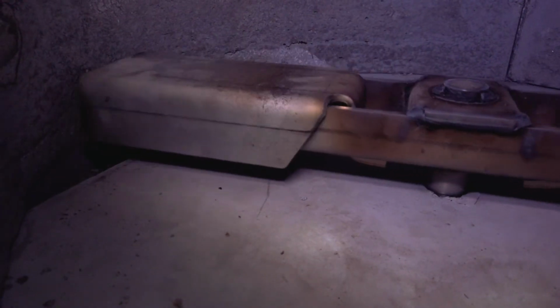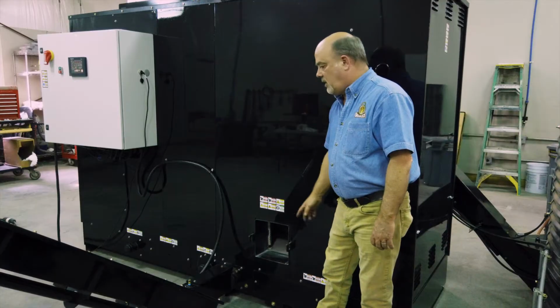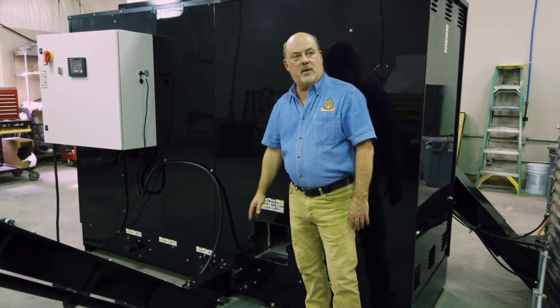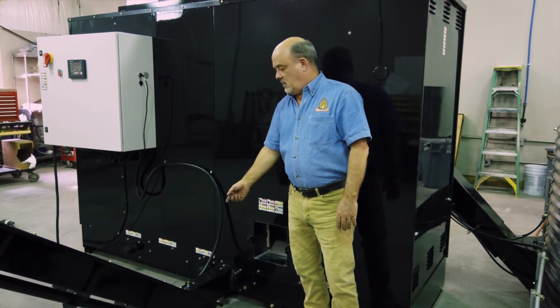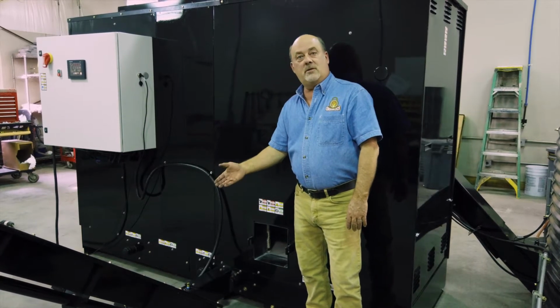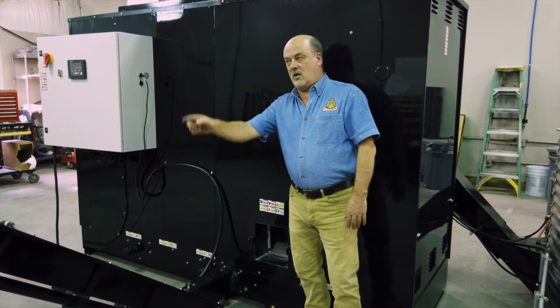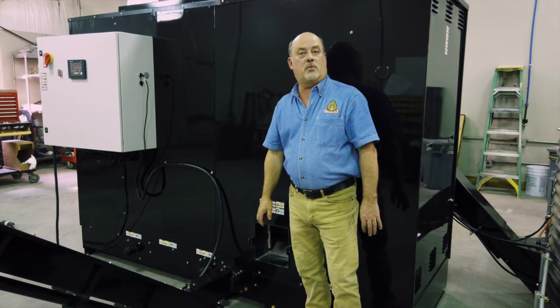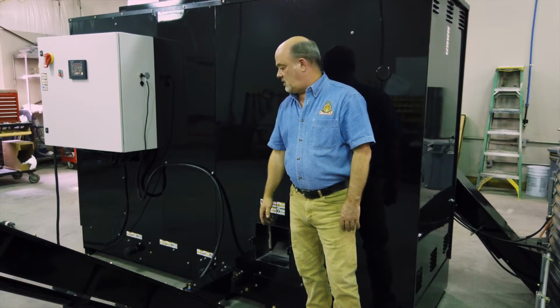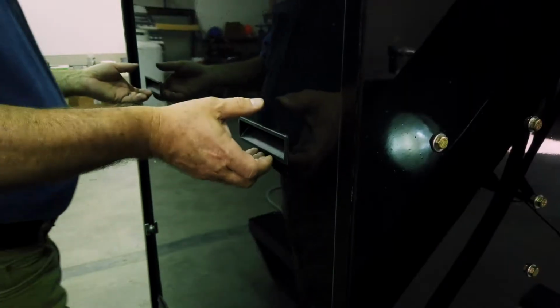And then inside there is where there's the pit where the ash falls out and goes into the biochar system. So when you're running biochar, actually very small amount of maintenance, because most of your burnt material never makes it to ash - it actually turns into char and you take it out here as a valuable product. So you have very little maintenance to do to the machine inside the firebox.